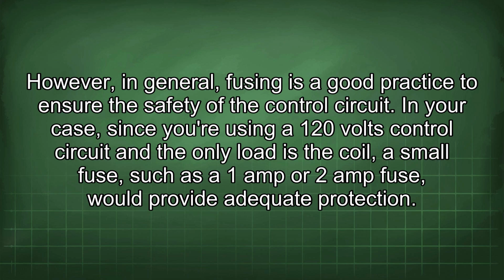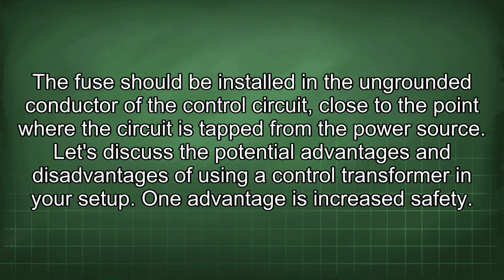In your case, since you are using a 120 volts control circuit and the only load is the coil, a small fuse, such as a 1 amp or 2 amp fuse, would provide adequate protection. The fuse should be installed in the ungrounded conductor of the control circuit close to the point where the circuit is tapped from the power source.